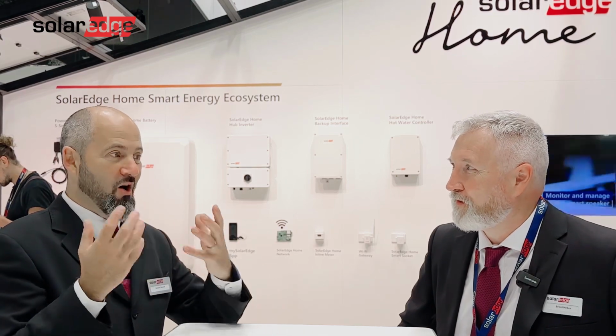So what I've seen on my system, and I've actually seen it on yours and some others as well, is you get this phenomenon where we can have temperature 20 degrees or less. We could still have the air mass at 1.5, so somewhere mid-morning, but our irradiance in Australia is way higher. That 1,000 watts per square metre is the global average. Australia isn't average, Australia is hot, you know. So if you're getting 12, 13, 1400 watts per square metre, which isn't unusual, we can actually see yield out of the module way high. I've seen it in excess of 410 watts on a 370 watt module.